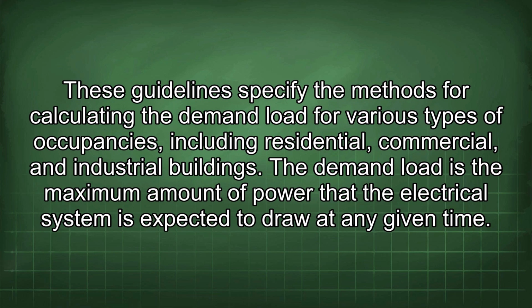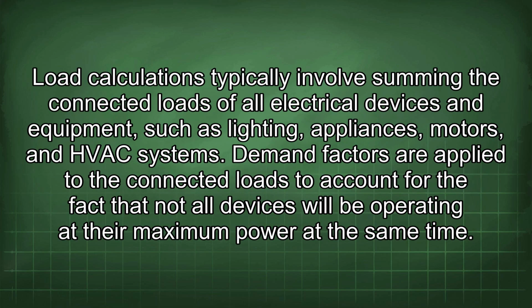Load calculations typically involve summing the connected loads of all electrical devices and equipment, such as lighting, appliances, motors, and HVAC systems. Demand factors are applied to the connected loads to account for the fact that not all devices will be operating at the maximum power at the same time.